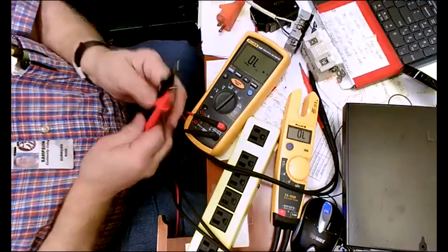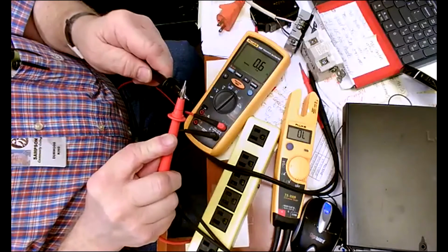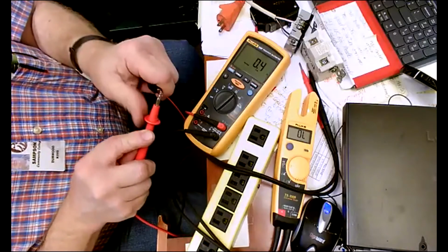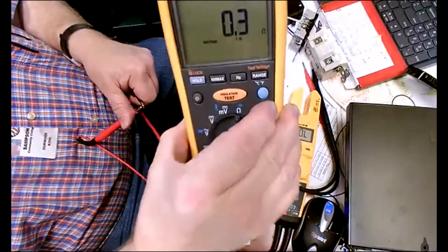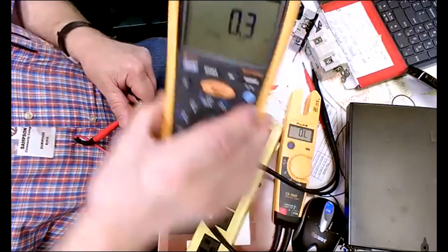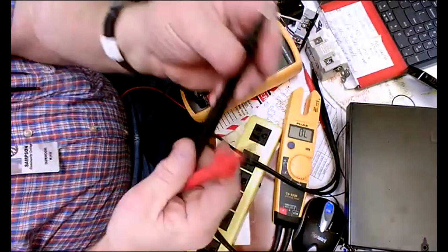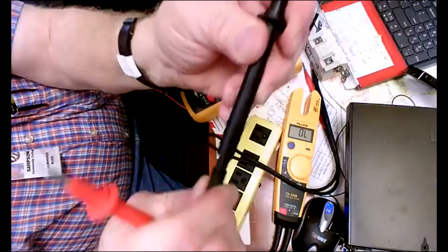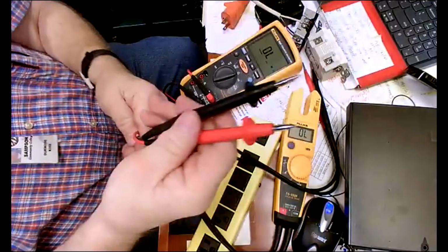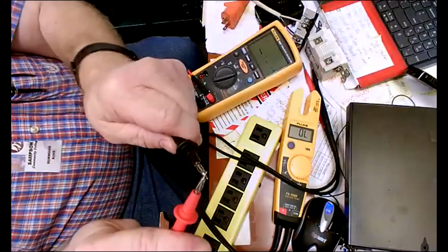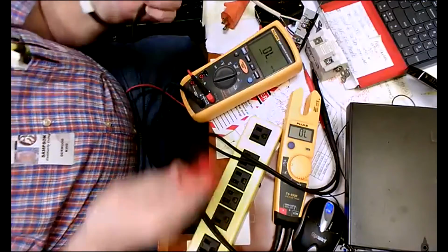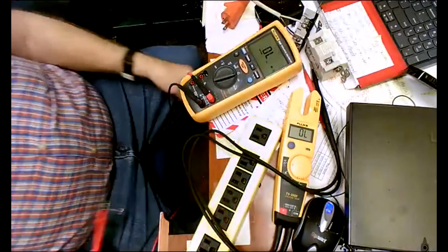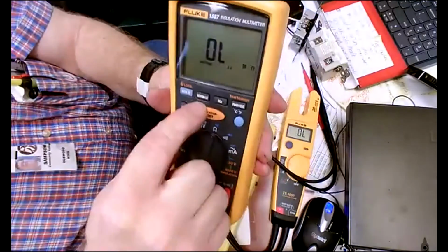But here you put these together, 0.6. You see that? 0.3 ohms. That's a lot better. Even though these have quick connects on them, it's just a much higher quality set of leads. So it's only a third of an ohm, the resistance of the quick connects and the leads themselves. This meter doesn't have a relative button, but if it has an REL button, you hit that while you've got the leads together, and it'll null that out.